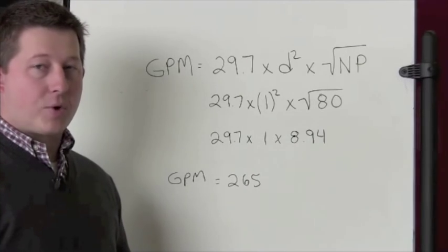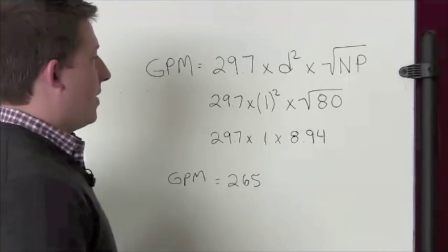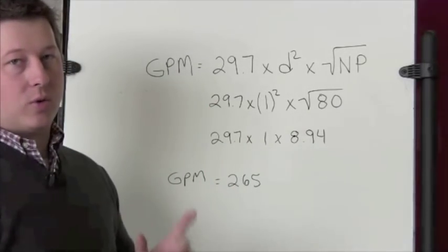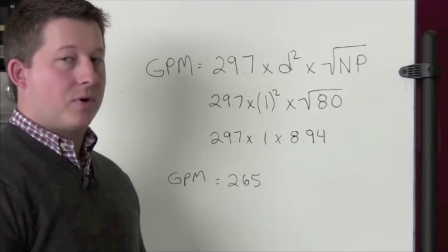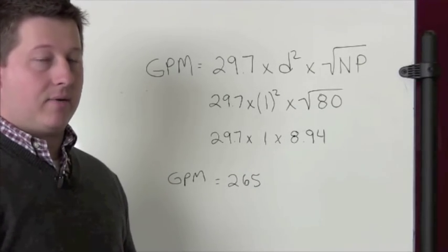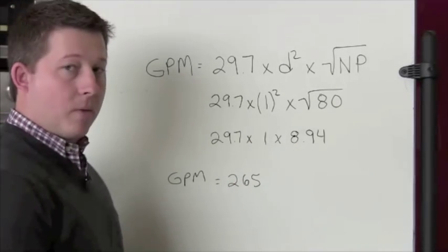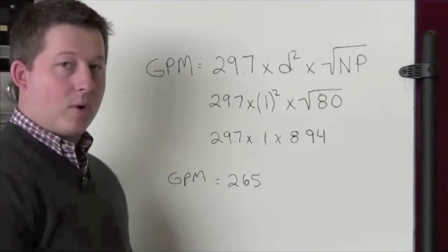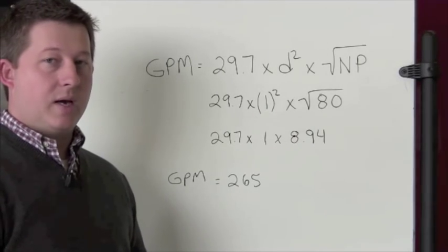I've written out the formula and worked it out on the board. We start off with 29.7 as the constant used in the formula. We multiply that times the square of the diameter — diameter squared — which is going to be one squared because we're using a one inch tip. And then we multiply that times the square root of nozzle pressure, which is 80 psi because we're using it as a master stream. So 29.7 times one squared is one, and the square root of 80 is 8.94. When we multiply it out, 29.7 times one times 8.94 gives us 265 gallons per minute coming out of that master stream nozzle at 80 psi.